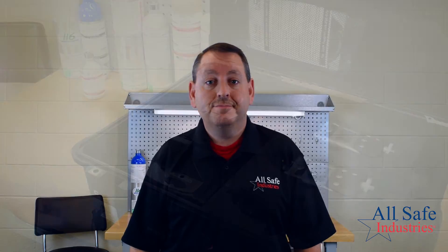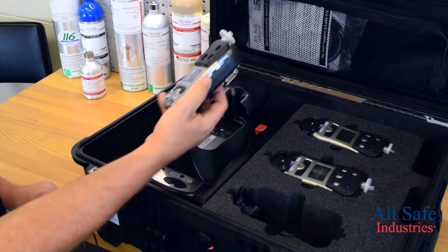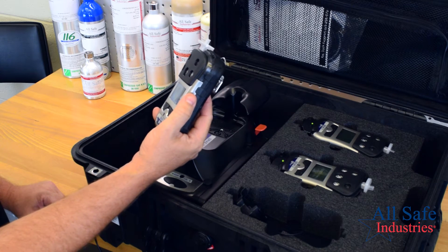If a bump test fails, the AutoRAE 2 cradle will automatically attempt a full calibration. To remove the meter, press the red release lever. Read the display to see the status of each test performed.